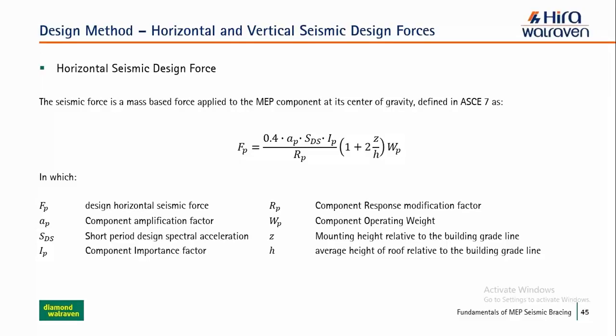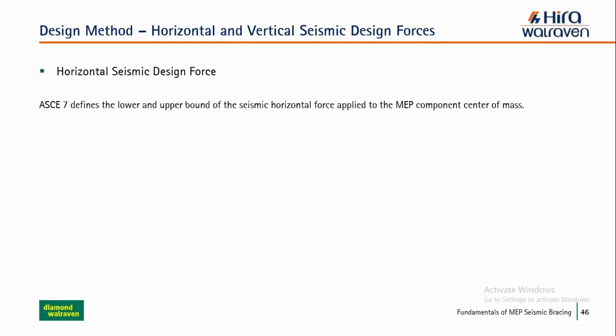Rp is the response modification factor, which is different for each equipment as per the different tables from ASHRAE standards. Then z over h, where z is the height of the point of attachment to the structure, and h is the overall height of the structure. Wp is your component operating weight, which should be the dynamic weight. So this is the method to calculate the seismic forces. The seismic force we have calculated here is the seismic force Fp.